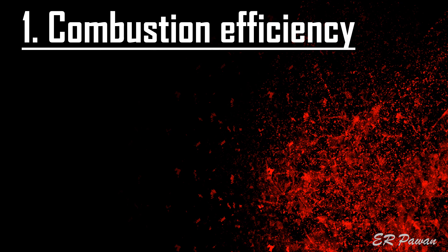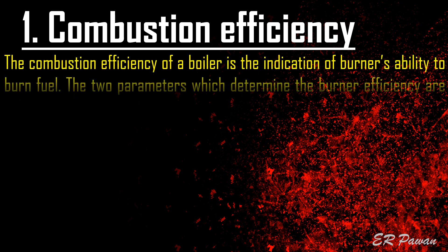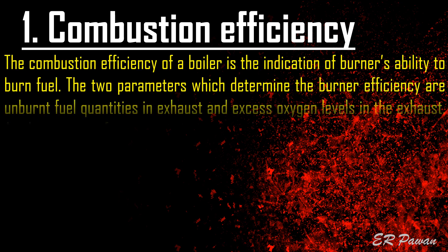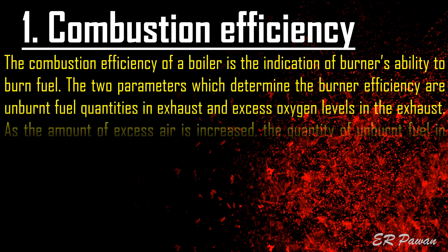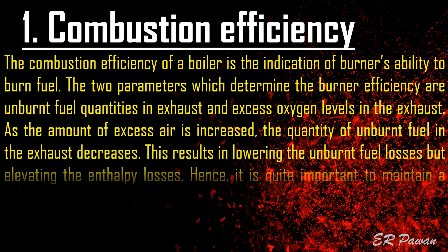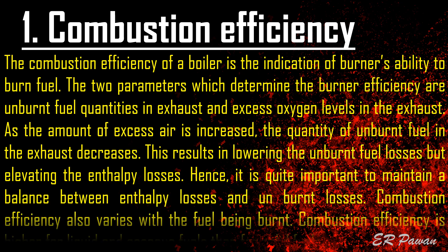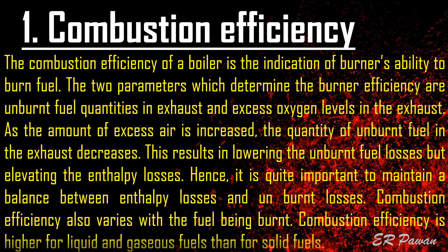Combustion efficiency of a boiler is the indication of the burner's ability to burn fuel. The two parameters which determine burner efficiency are unburned fuel quantities in the exhaust and excess oxygen levels in the exhaust. As the amount of excess air is increased, the quantity of unburned fuel in the exhaust decreases, lowering unburned fuel losses but elevating enthalpy losses. Hence, it is quite important to maintain a balance between enthalpy losses and unburned losses. Combustion efficiency is higher for liquid and gaseous fuels than for solid fuels.